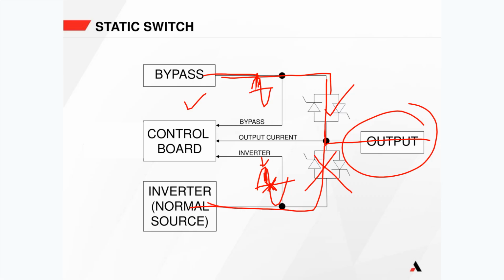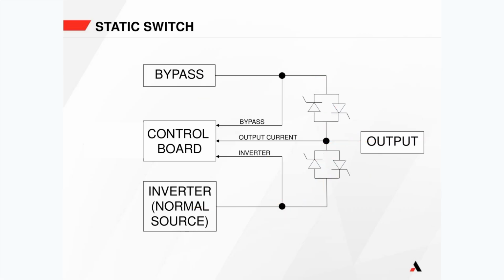through a static switch, because you're always going to be pressing the button, or the transfer is near enough always going to be taking place somewhere in that half cycle where both power supplies are going to be supplying in parallel for a very short period of time. And because they are in sync, that's not a problem. If they weren't in sync, that would be a problem. So that is how a static switch uses SCRs to create a switch with no moving parts.